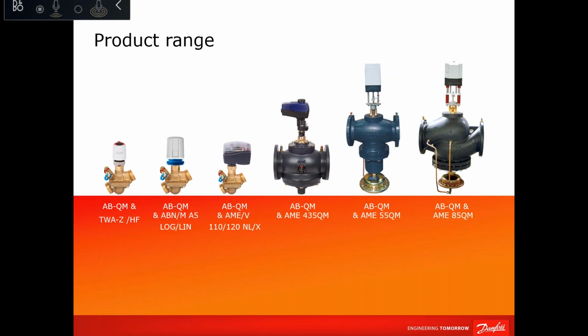So if we take the full product range, we have from DN10 low flow up to DN250. Here you can see all these brass types are for FCUs, and in most cases we only propose the gear type actuator. Why? Because we want to see the actual savings from the valve. So you need full modulation and full pressure independency.